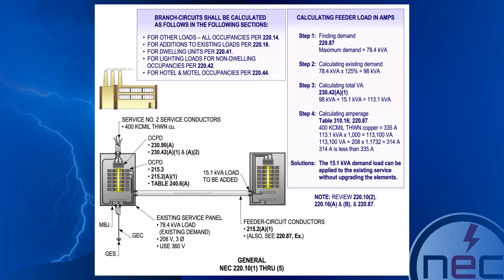A revision has been made to clarify and correlate with actions taken during the first revision stage. Loads necessary for branch circuit calculations are included in the new list items under 220.10 General. The code making panel's action during the first draft relocated multiple sections to Part 3, Feeder and Service Load Calculations. While those relocated requirements do apply when calculating feeder and service load calculations, they are also applied when calculating branch circuit loads. Rather than repeat requirements in both parts 2 and 3, a list is created in section 220.10 that identifies all sections within 220 that apply to branch circuit load calculations.